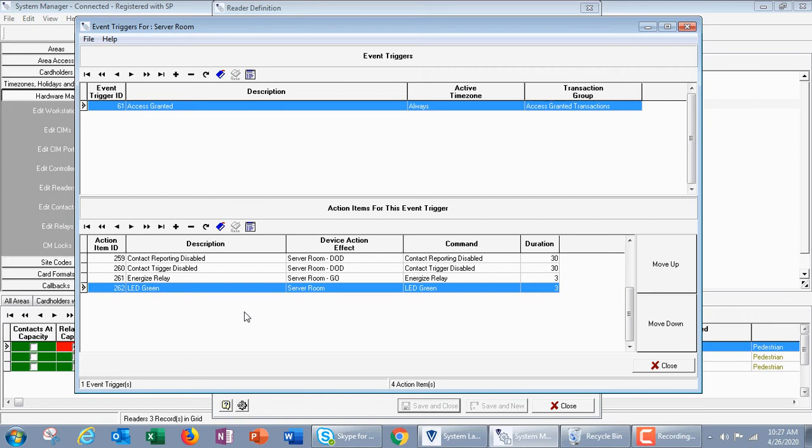If you've got a motion sensor request to exit, after a valid access, you're going to open the door, walk through the door, and you'll walk through the motion. So we're going to disable the motion sensor request to exit from reporting and disable the motion sensor triggers from unlocking the door, right? We don't need those to happen on a valid access. That's the way the template's programmed.